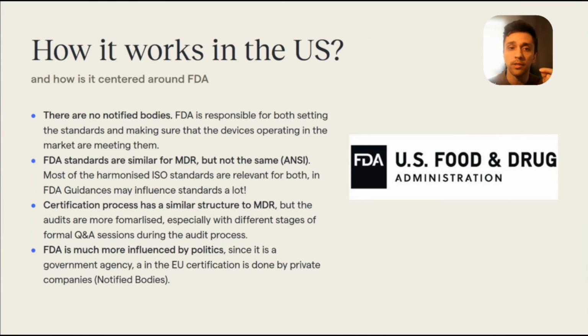So you may have a situation that you implement a standard, you say, okay, I'm doing everything according to a standard, and then you apply to FDA, and FDA says, hey, this standard is harmonized, but we have changed it in this and this area, in this guidance, and you should follow our guidance. So it is very important to also implement their guidances and know what they are recommending for applying the standards.